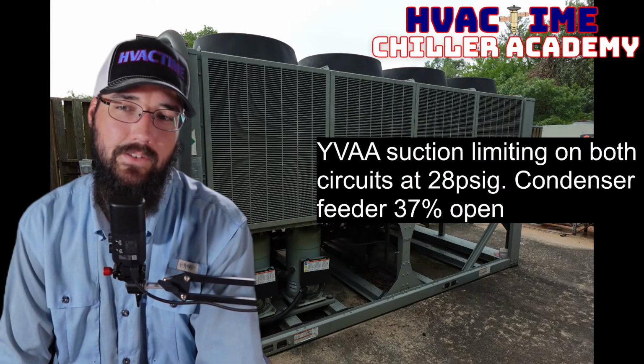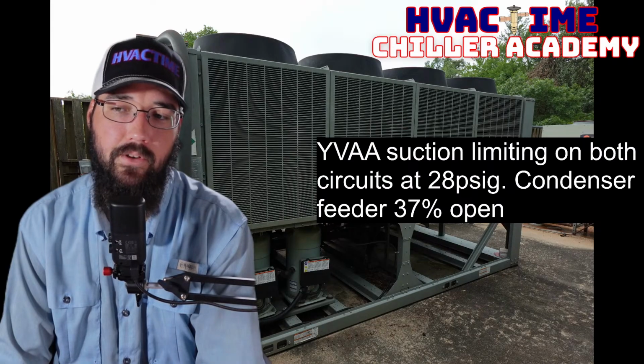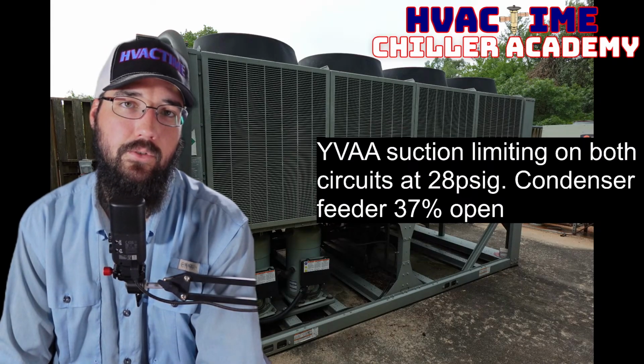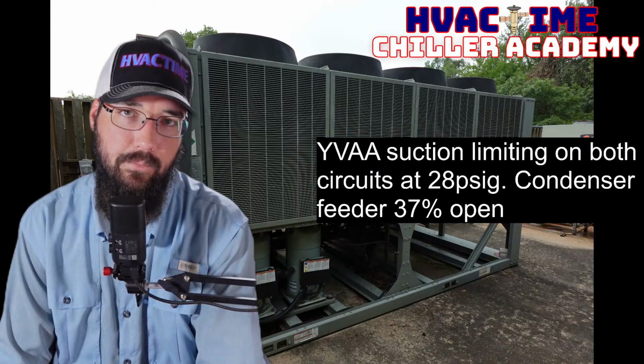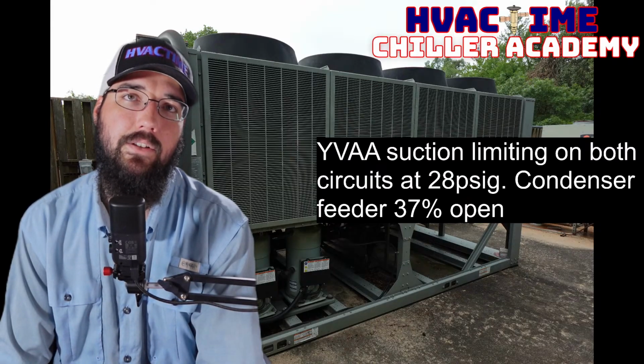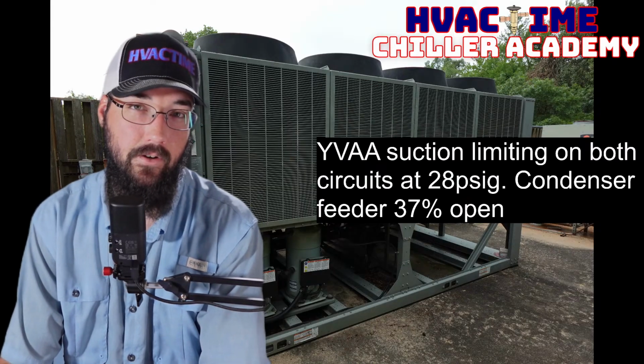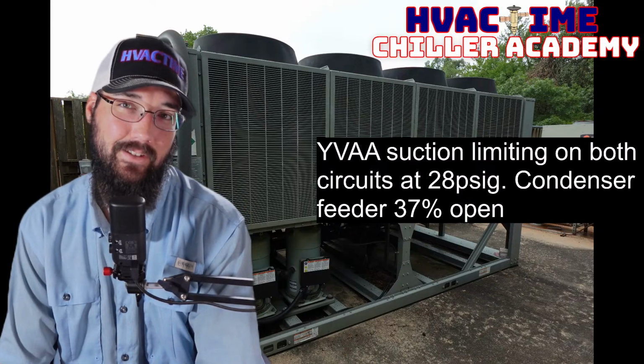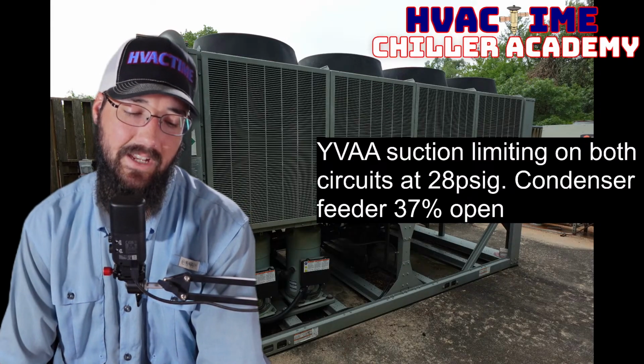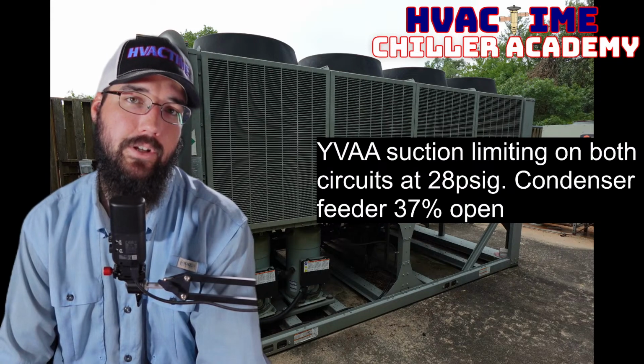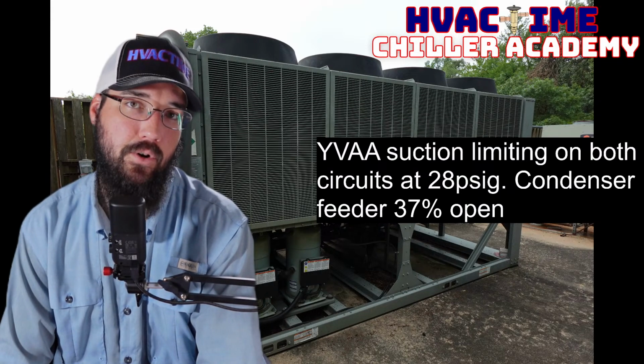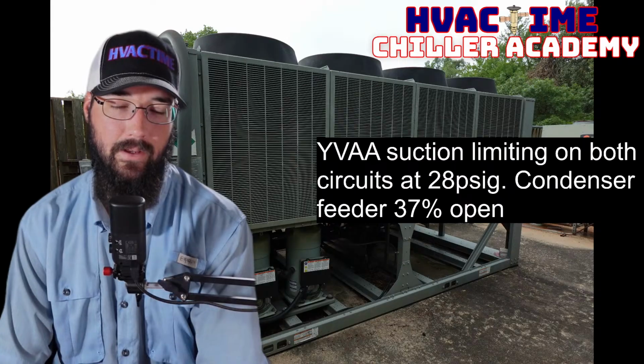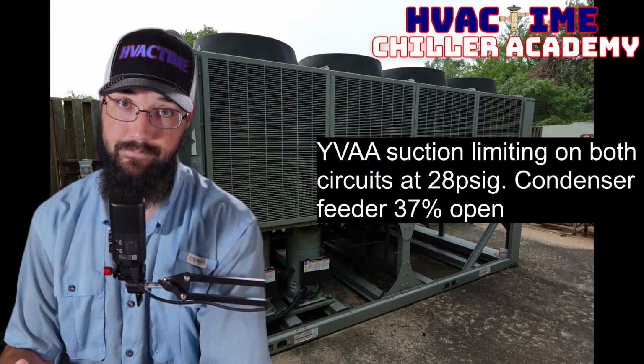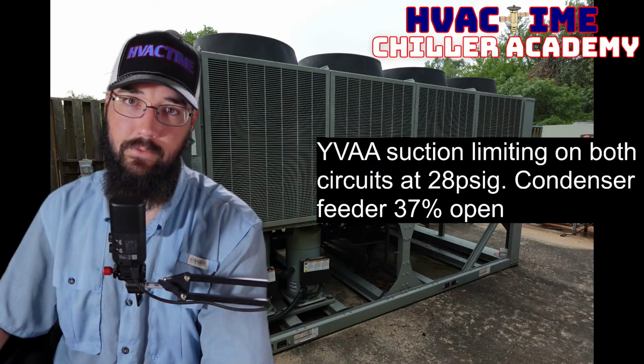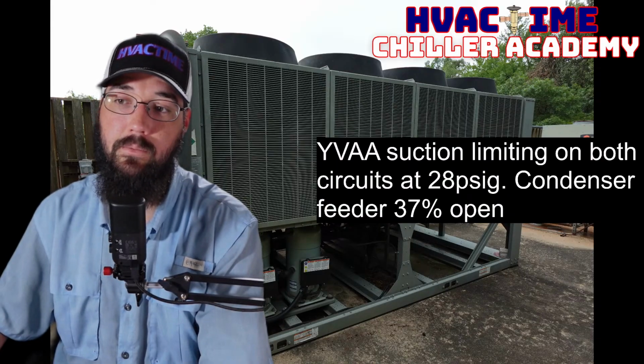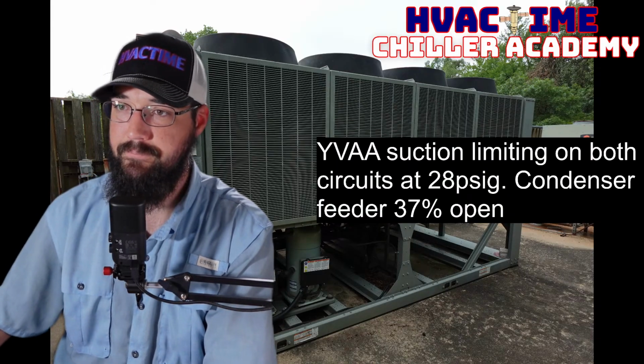Because my gut says it's probably evaporator flow. You've probably got a flow problem on the evaporator, and it's causing both circuits to respond the way they are, being that they're that consistent. Because technically, charge and oil migration, I wouldn't expect to be that perfectly aligned, but they could be. So we have to be very careful with the assumptions that we make at any given time.